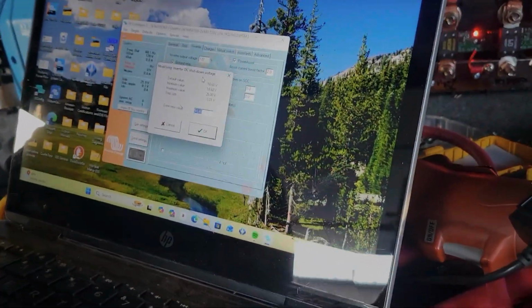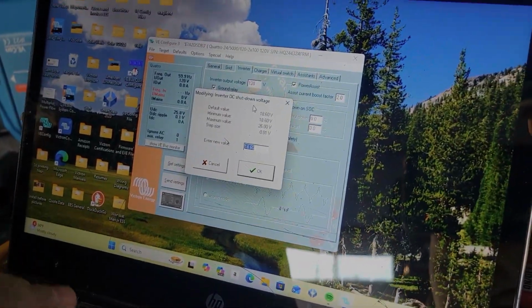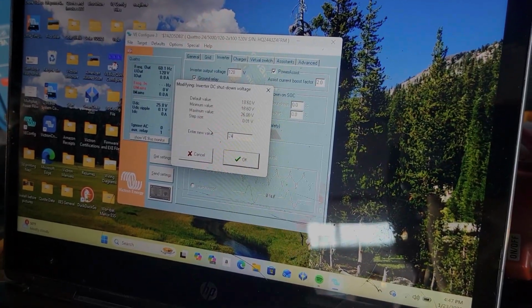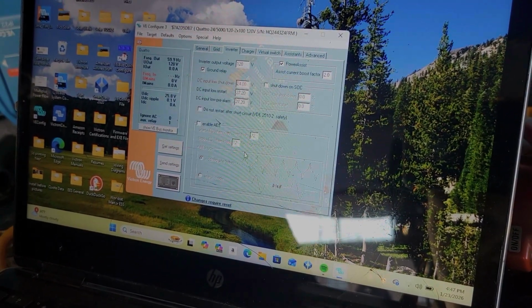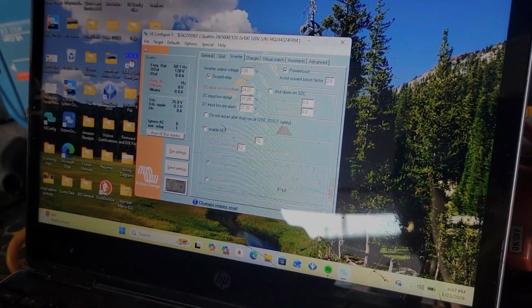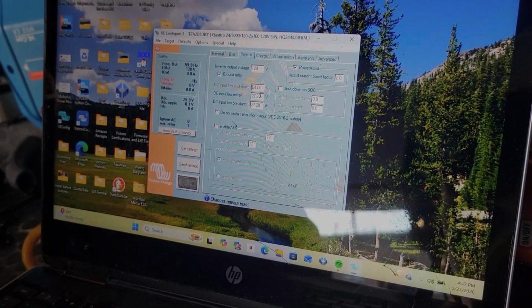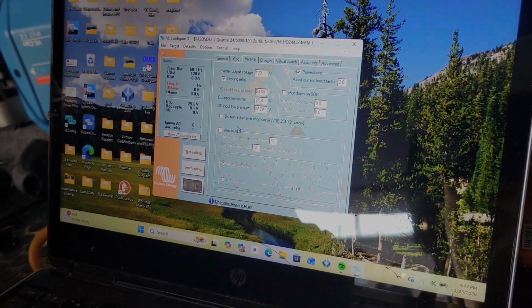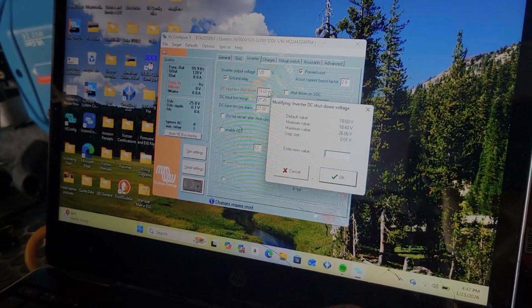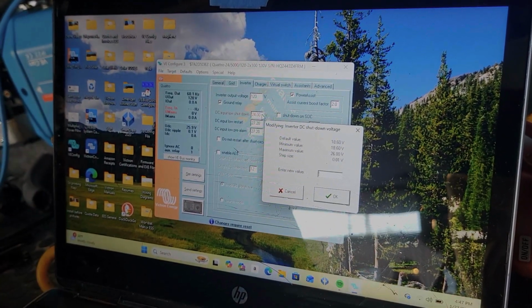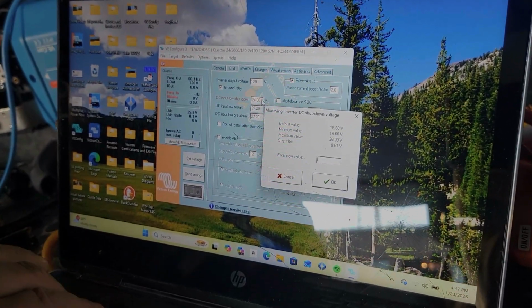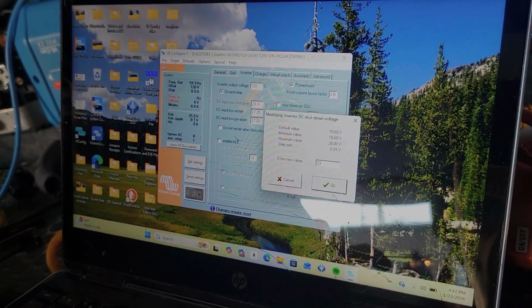So, all right, now we're going to set the input shutdown. Typically with lithium, we want to shut down the battery at 24 volts. So that's going to be our hard shutdown voltage. Now we can push that a little bit farther, and let's say we can go to 23, because 11.5 is usually a good shutdown voltage on a 12 volt system. So on this, we'll say 23.